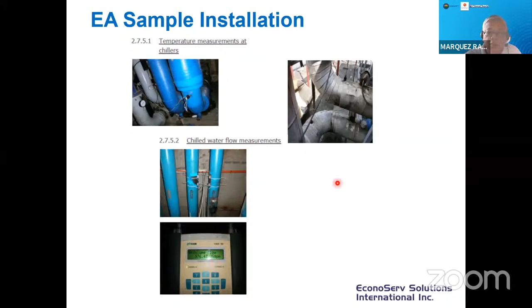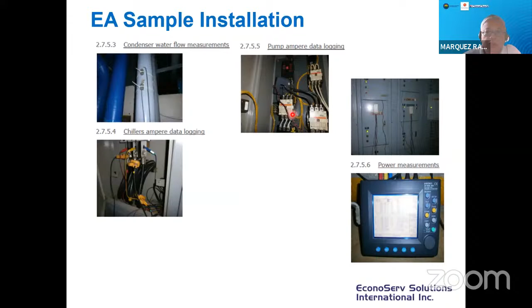Now this is an example of an installation to measure chilled water flow, with the flow meters and sensors where they are to be installed. That's on the chilled water side. This is the condenser water side. Then you have the pumps, in terms of power or current. In terms of safety guidelines, you have PPEs, safety shoes, scaffolds if needed, rubber gloves rated 600 volts or 1000 volts and below, and equipment grounding. For mechanical, sometimes we do stoppage because we have to install the pressure or temperature sensors.